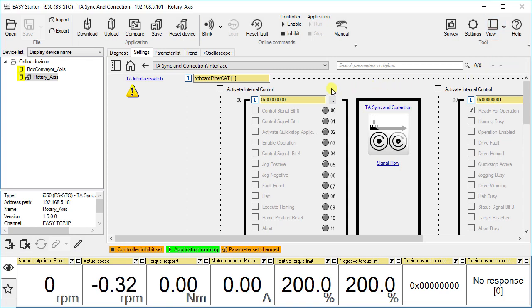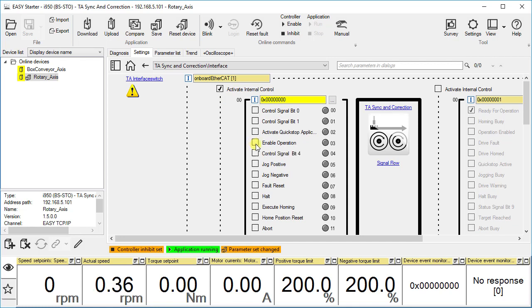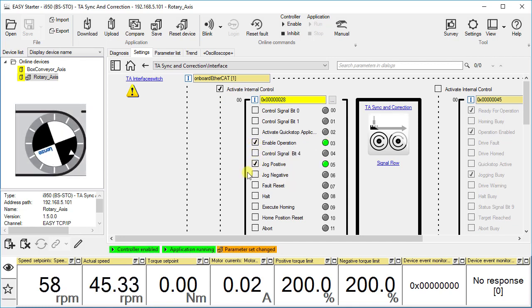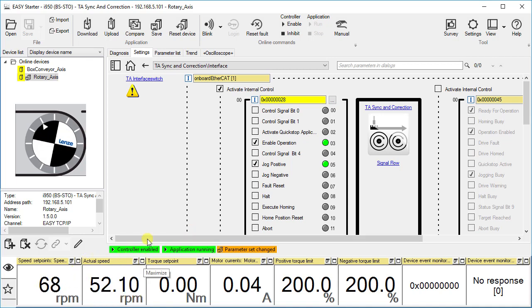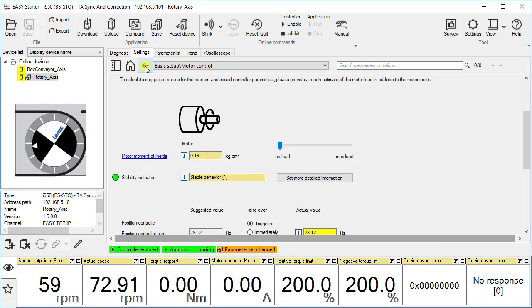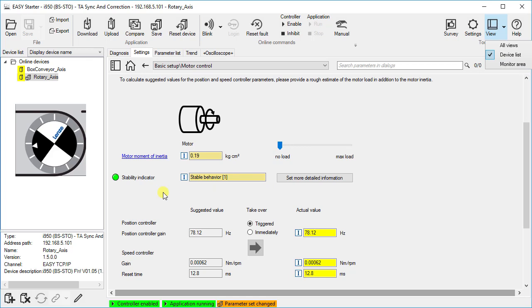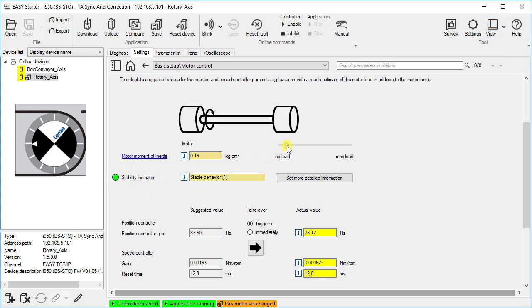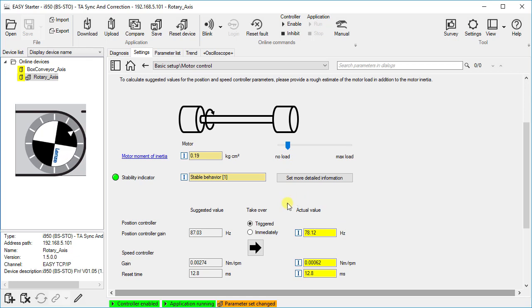We start the drive with the internal controls. Enable operation. Jog positive. The drive moves at the set jog speed of 60 rpms. The stability indicator shows stable behavior. We move the slider to the right, and nothing happens. The suggested values are only accepted in the controller by the confirm button.